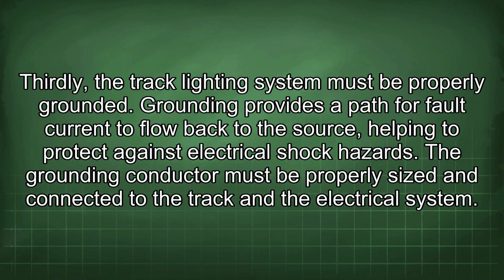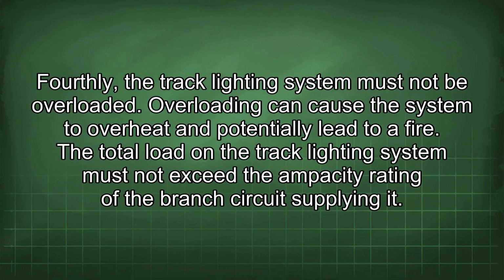maintenance. Thirdly, the track lighting system must be properly grounded. Grounding provides a path for fault current to flow back to the source, helping to protect against electrical shock hazards. The grounding conductor must be properly sized and connected to the track and the electrical system. Fourthly, the track lighting system must not be overloaded. Overloading can cause the system to overheat and potentially lead to a fire. The total load in the track lighting system must not exceed the ampacity rating of the branch circuit supplying it.